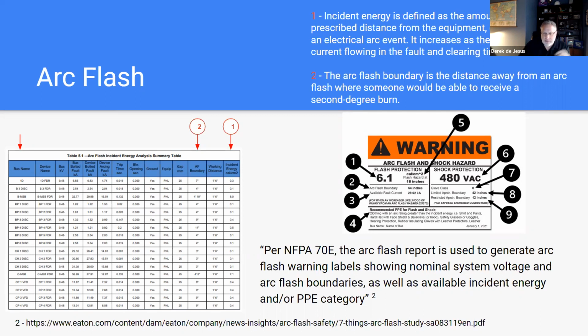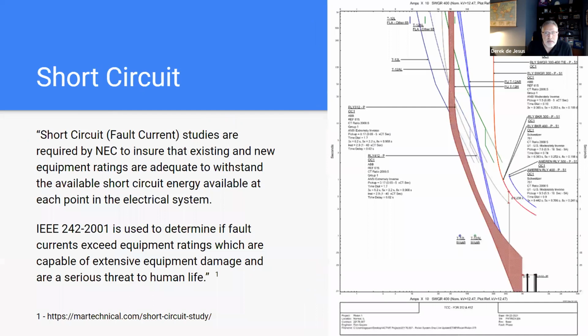So the second part of his question was, what information is actually needed to create the study when having a new board? You're going to have to get utility information as far as their available short circuit fault from their incoming line. The electrical contractor is going to have to provide the cable lengths of all of their feeders to the individual developing the study, because they need to put that into the one line. I do not have one in here, but I think we do talk about the feeder lengths on this study.